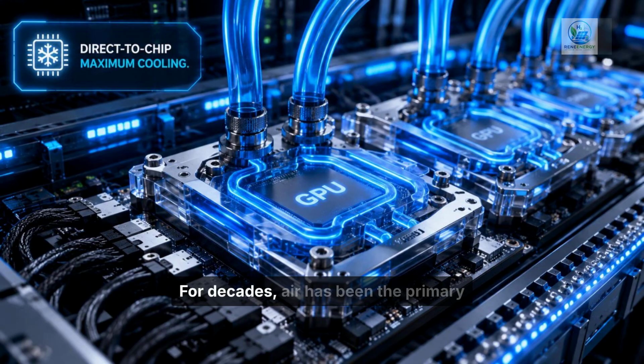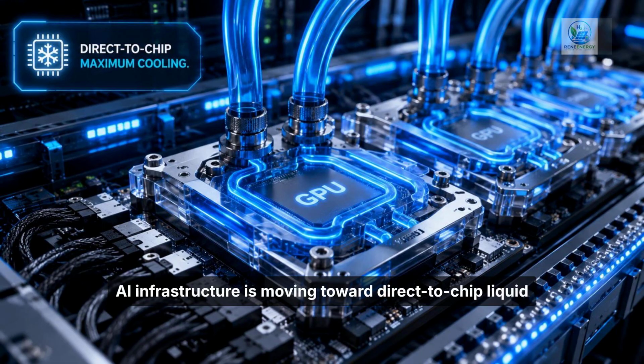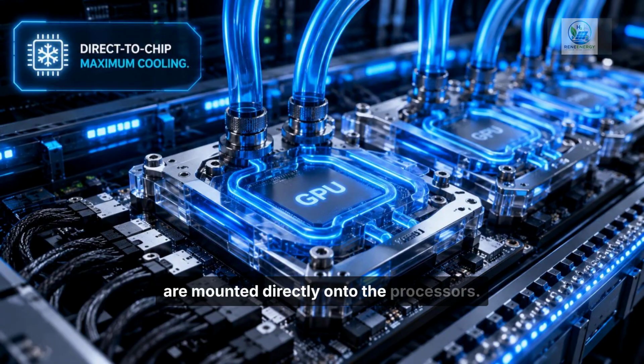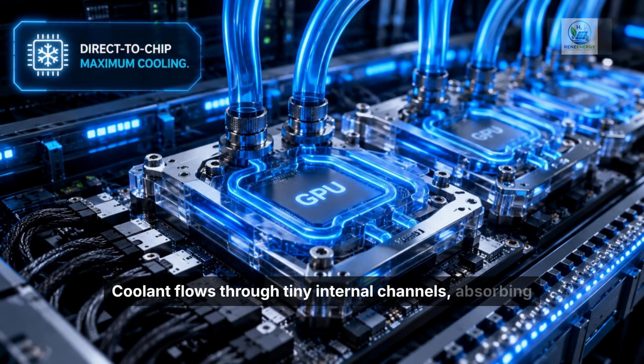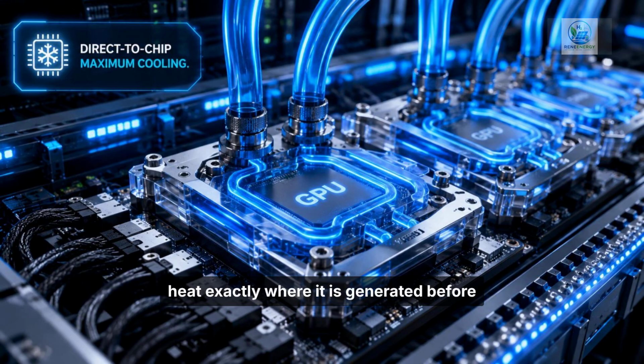For decades, air has been the primary method of cooling computers. But today's AI processors are producing so much heat that air alone is no longer enough. The next generation of AI infrastructure is moving toward direct-to-chip liquid cooling. Instead of cooling the entire server with moving air, specially engineered cold plates are mounted directly onto the processors. Coolant flows through tiny internal channels, absorbing heat exactly where it is generated before carrying it away through a closed liquid loop. Because liquids transfer heat far more efficiently than air, this approach supports faster processors, denser server racks, lower fan power, and significantly improved energy efficiency. As AI models continue growing, direct liquid cooling is rapidly becoming the new industry standard.